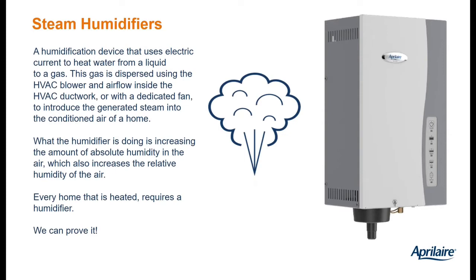Our steam humidifiers use electricity to heat water to boiling and then into steam. The steam then travels down a steam tube and either gets introduced into the HVAC ductwork — with the HVAC blower absorbing the steam and dispersing that humidified air throughout the home — or, towards the end of the webinar, we'll talk about a fan pack that gets installed separate from the HVAC system with its own small fan. Conceptually, what we're doing is adding absolute humidity — grains of moisture, molecules of water — which increases the relative humidity of the home for occupant comfort and health, as well as wood furnishings and musical instruments.